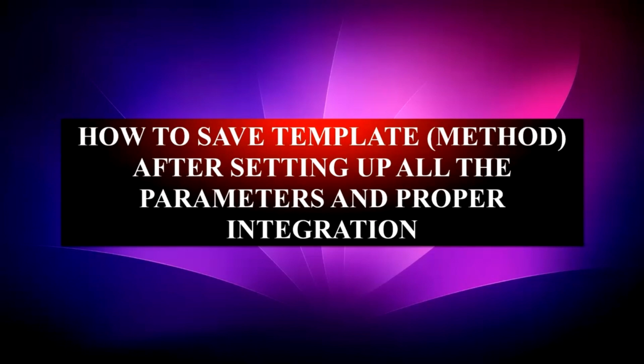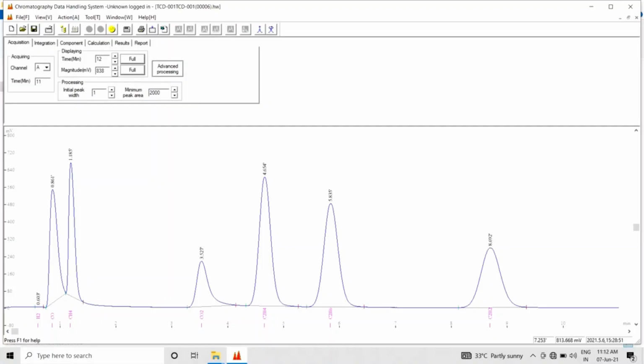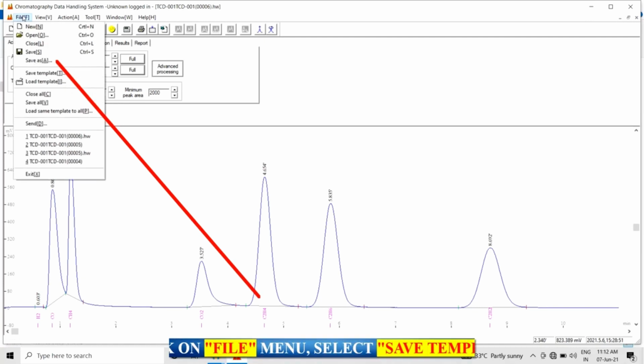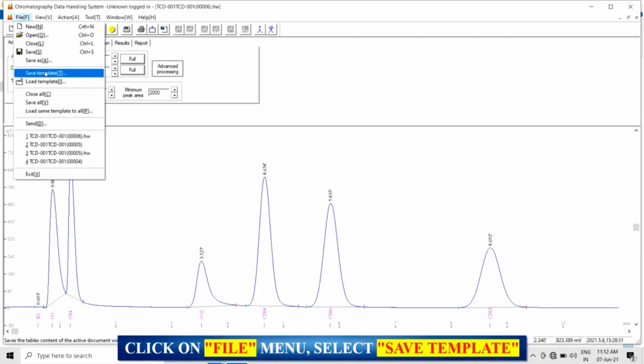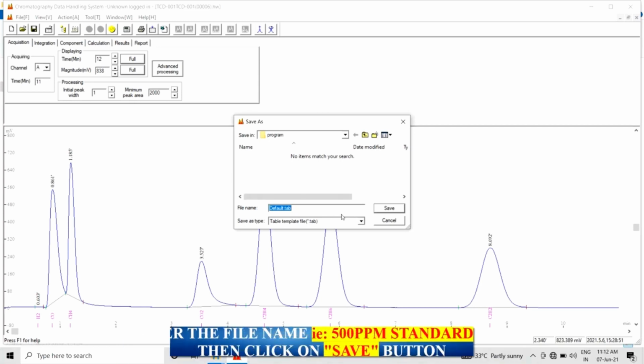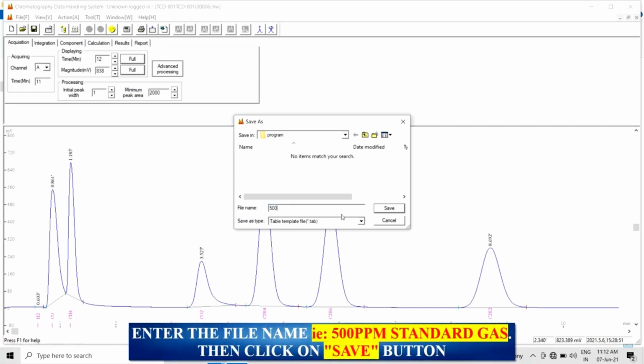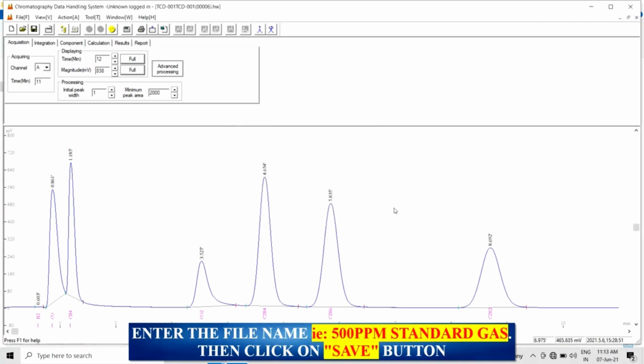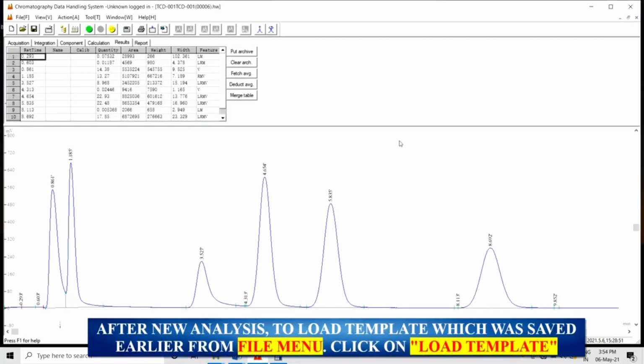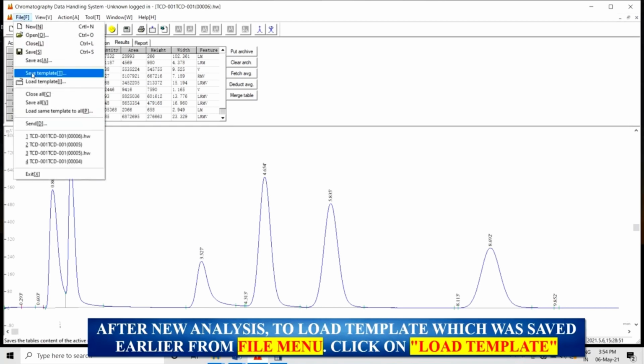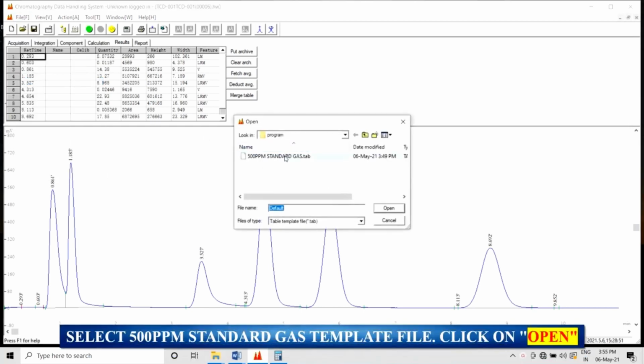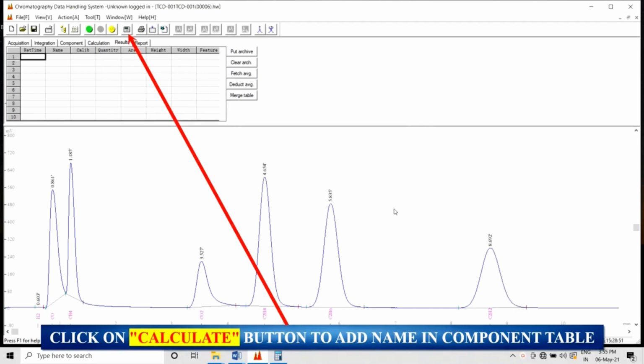How to save a template or method file after setting up all the parameters and proper integration. Click on the File menu, select Save Template. Enter the file name, for example, 500 ppm standard gas. Then click on the Save button. After a new analysis, to load the template which was saved earlier, go to the File menu and click on Load Template. Select the 500 ppm standard gas template file and click on the Open button. Click on the Calculate button to add names in the component table.